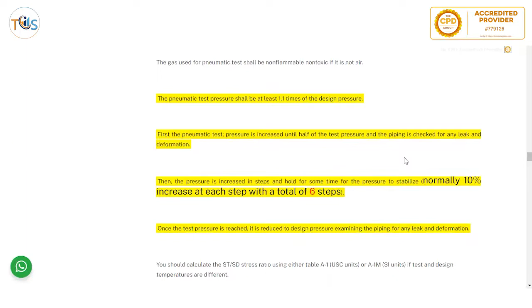First, the pneumatic test. During the pneumatic test, the pressure is increased up to half of the test pressure, and the piping is checked for any leak and deformation. So up to half, 50%. You don't go straight away to 100%. Then in steps, you increase it. Once it's stabilized on the pressure gauge, you wait for some time and increase it by 10% a step, and every time you wait till it's stabilized. So the total takes 6 steps, 50% plus 10% steps. They might ask you what is the total number of steps of pneumatic test in the exam.